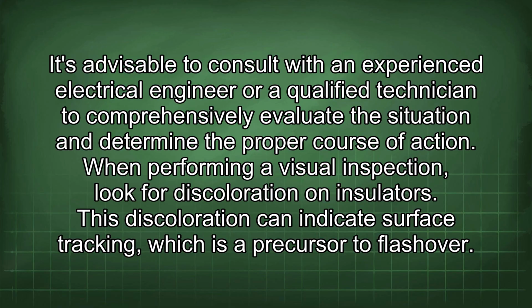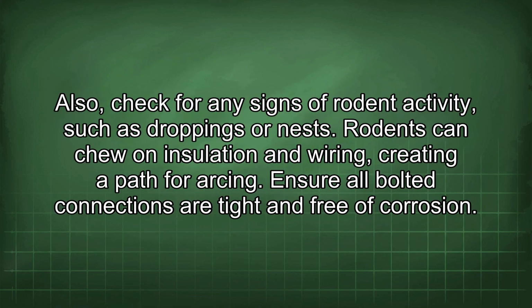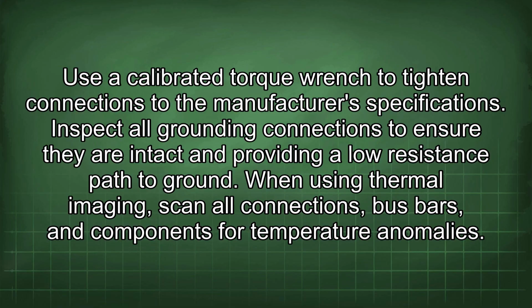When performing a visual inspection, look for discoloration on insulators. This discoloration can indicate surface tracking, which is a precursor to flashover. Also, check for any signs of rodent activity, such as droppings or nests. Rodents can chew on insulation and wiring, creating a path for arcing. Ensure all bolted connections are tight and free of corrosion. Use a calibrated torque wrench to tighten connections to the manufacturer's specifications. Inspect all grounding connections to ensure they are intact and providing a low resistance path to ground.